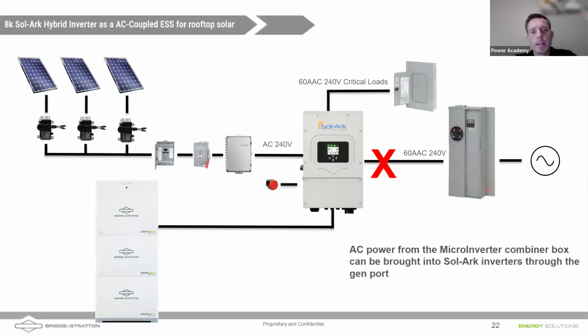In the event that the battery fills up and the loads of the house are not consuming all of that power, we need to be able to shut that power down or reduce it, and that's done by frequency shifting. The Sol-Ark inverter is able to control the output of 1741 inverters, like those Enphase inverters, by frequency shifting. You'll notice the frequency of the Sol-Ark will go up when those batteries are full, up to 63 hertz, to shut off that microinverter system.